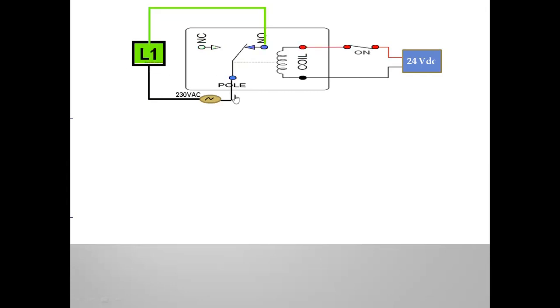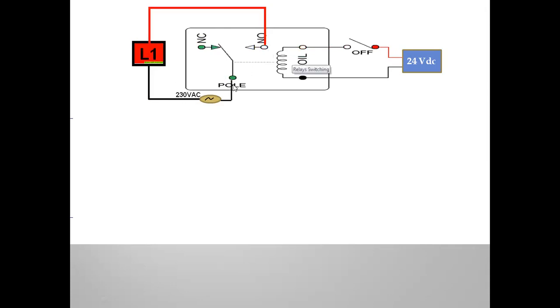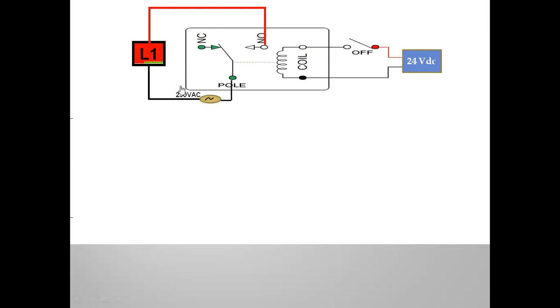Across this pole, I have connected some supply — it is providing supply to the lamp. From PLC, I am getting 24 volts DC only, but for your output, we require 230 volts AC. For connecting a contactor also, we need 230 volts AC supply. So at the secondary end I am providing the output supply, while at the primary end I am giving only control DC. That is the advantage with the relay — we are converting the supply.